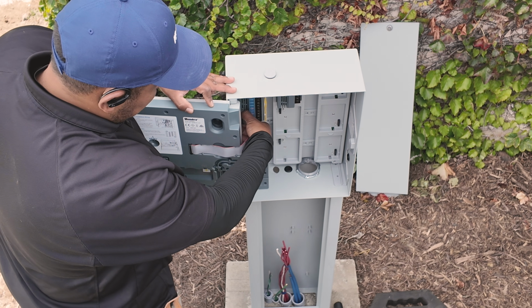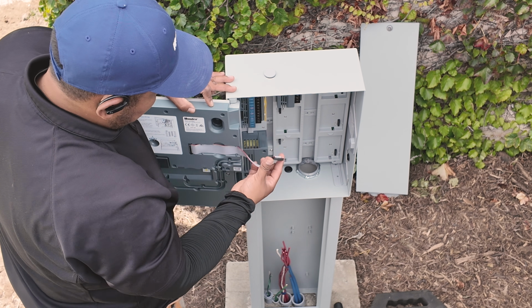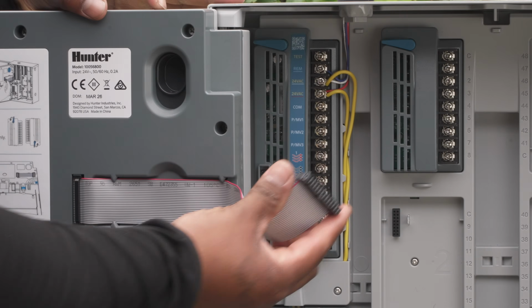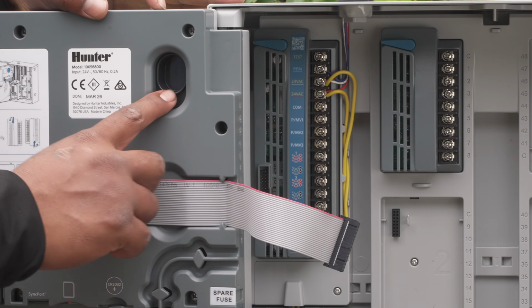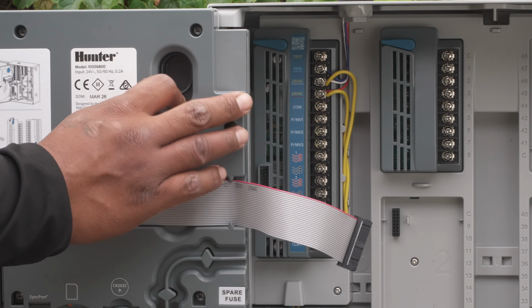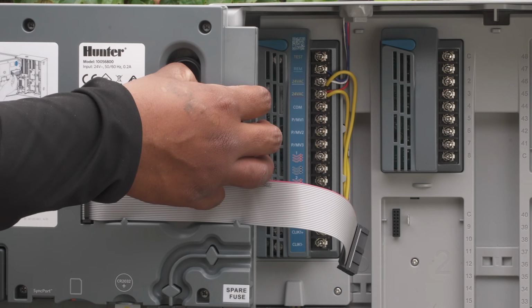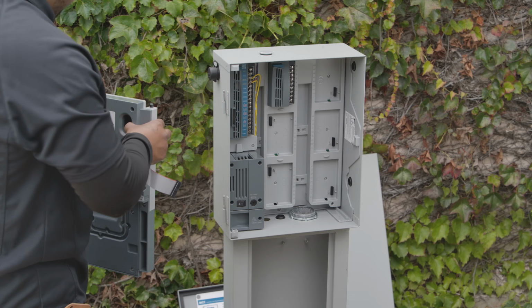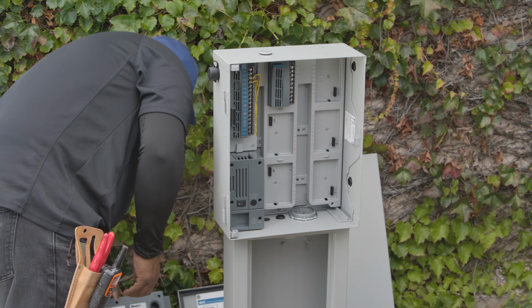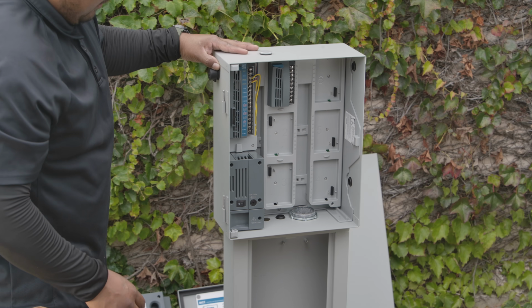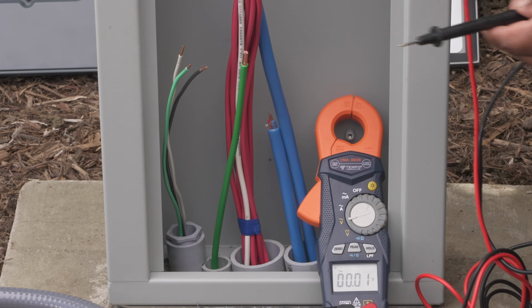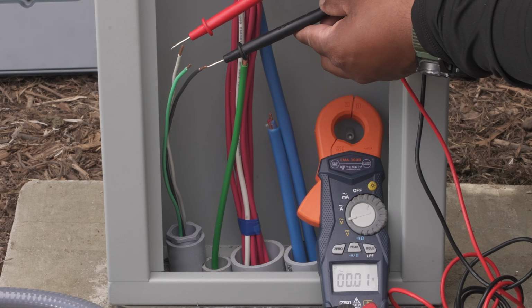Gently unplug the cable from the housing, leaving it connected to the face pack. While holding the face pack in place, press down on the black release slider to disconnect the top hinge. You can now remove the face pack from the controller housing for easier access to the wiring compartment. Make sure the incoming electrical power is off during these steps.